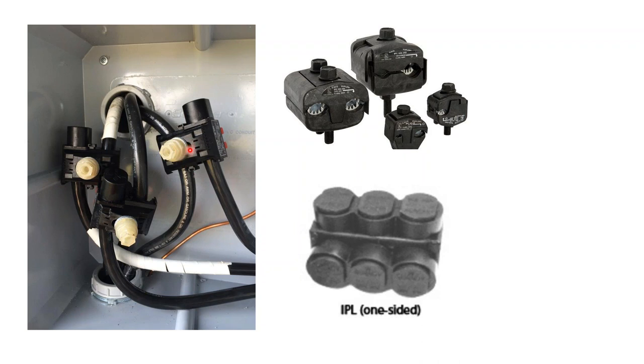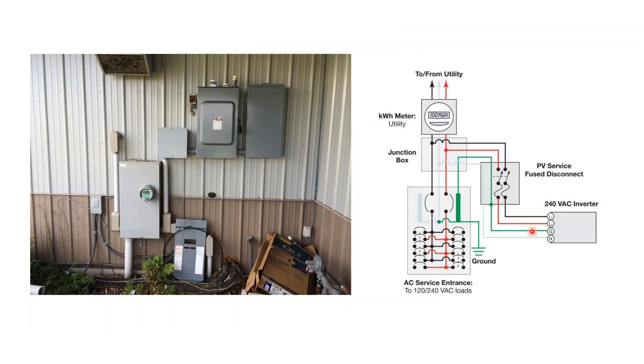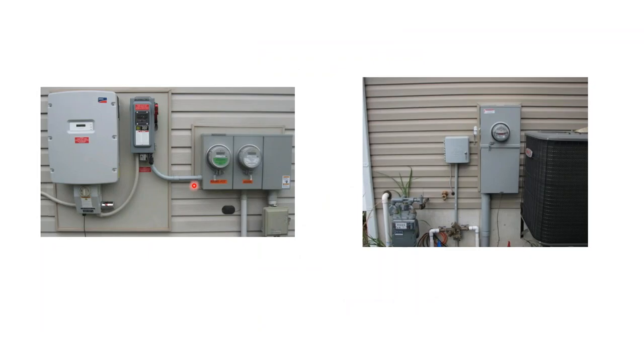But from going around the country and talking about these things, I run into more electricians who recommend staying away from them and using a regular tap than electricians who support them. So I've moved back to the traditional tap connectors inside these boxes. Here we have our line side tap between the meter and the service panel. Or if you just had a microinverter circuit, you could do a meter disconnect combo box and land your microinverters onto the service load center.